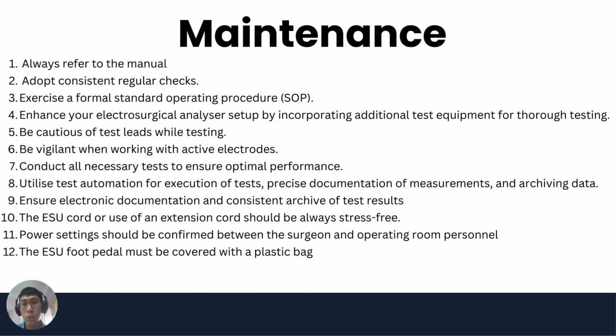Fourthly, enhance your electrosurgical analyzer setup by incorporating additional test equipment for thorough testing. Many manufacturer performance inspection protocols necessitate electrical safety assessments, such as ground wire resistance and chassis leakage tests. To ensure easy completion of the electrical safety component of the performance inspection, have an electrical safety analyzer readily available.